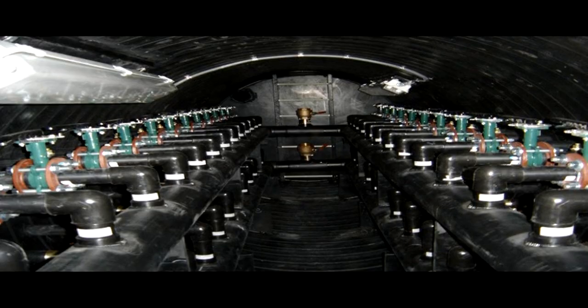So what we're doing is at each one of those circuits I showed you earlier, a supply and return line comes in. The red indicates supply, the green on top, we haven't connected those pipes yet, that's return. Basically each one of these represents a string of 12 500-foot holes that runs into the vault. We then manifold that in the vault, run into this 8-inch pipe. As you can see, I'll come in with balance valves and circuit setters so we can adjust and balance everything. At the very far end, you see the 2 brass valves. That's our flushing and purging ports, so we can clean the system out and purge it of all the air and induce the glycol.